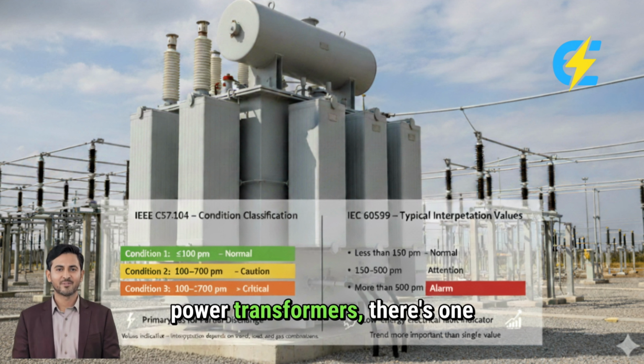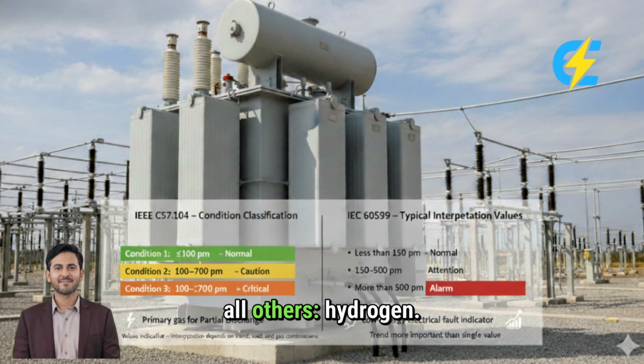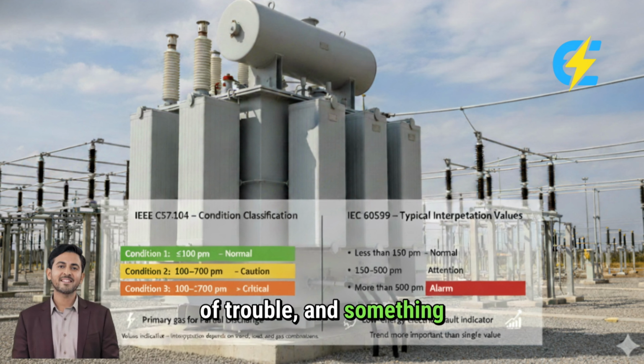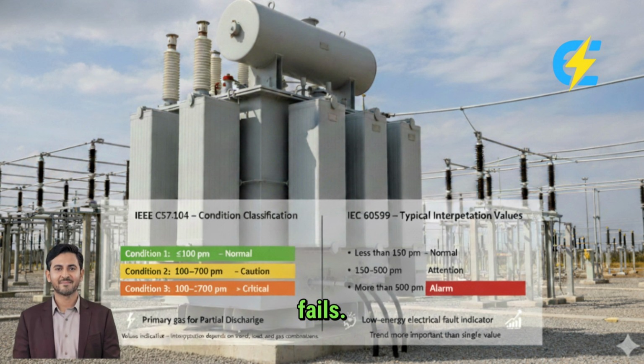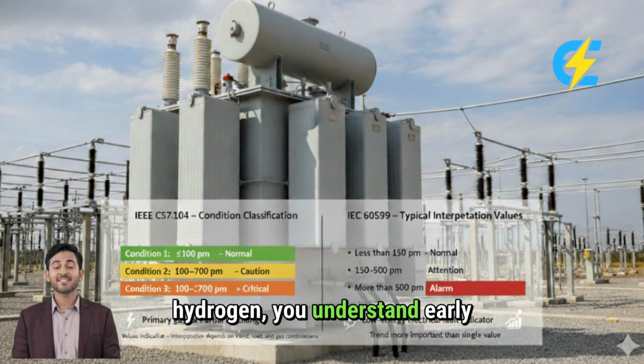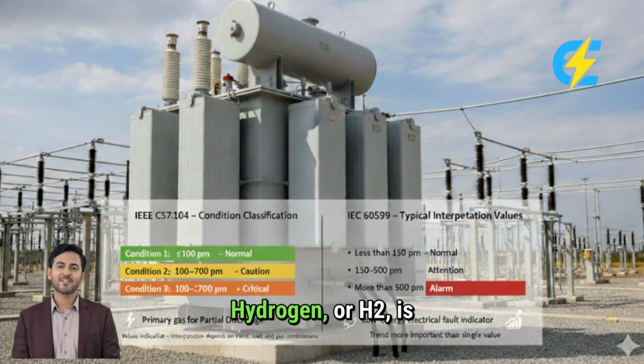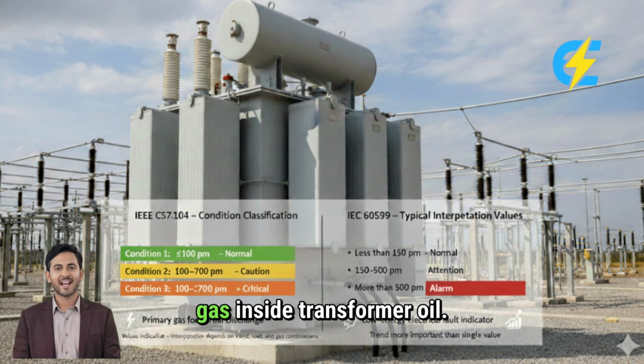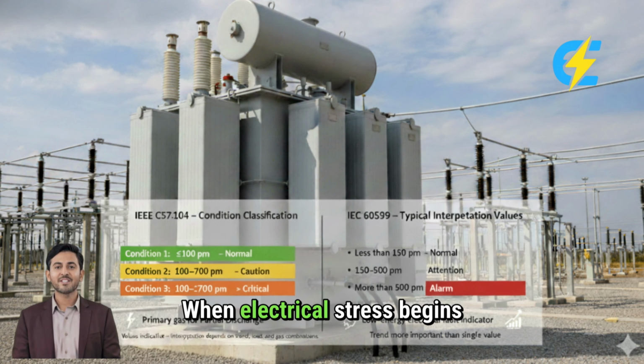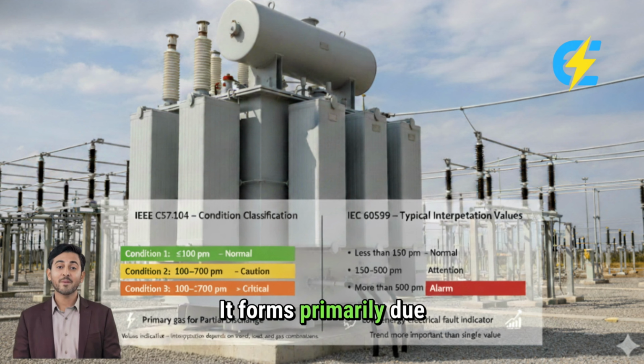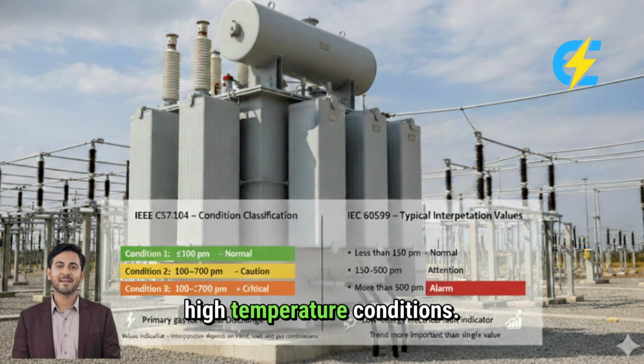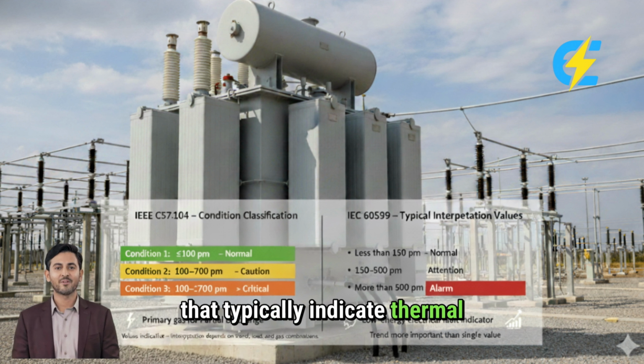In the world of power transformers, there's one gas that speaks before all others: hydrogen. It's the earliest warning signal, the first whisper of trouble, and something that can save a transformer long before it fails. If you truly understand hydrogen, you understand early transformer warnings. Hydrogen, or H₂, is the lightest and fastest forming gas inside transformer oil. When electrical stress begins to develop within a transformer, hydrogen is the first gas to appear. It forms primarily due to electrical stress, such as partial discharge or corona activity, rather than high temperature conditions. This makes it fundamentally different from other gases that typically indicate thermal faults.